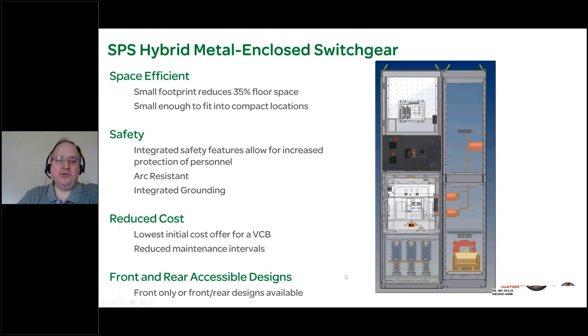And then the third item is integrated grounding. Do not underestimate the benefits of integrated grounding. When I show it on paper like this, people tend to ignore it or pass over it or see it as a minor benefit. But once the equipment actually arrives in the plant, the maintenance people are used to opening up the disconnect source, either the load break switch or a circuit breaker, getting into category 4 PPE, getting into the appropriate voltage rated PPE, opening up the equipment, verifying absence of voltage, and then using hot sticks to attach. They attach the ground cable with their hand to ground, but then they use a hot stick to attach to each of the 3 phases.